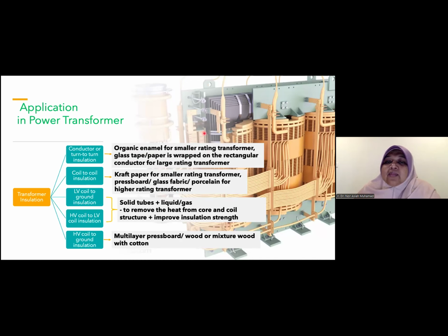Then we have the insulation between low voltage and high voltage. In here we have an insulator as well. We have a solid tube, and we have liquid here. The winding will be submerged in the oil. There will be oil here, or gas, if it is a gas type. This is to remove heat, because there is flux induced here, and then there is heat from the core and coil structure.